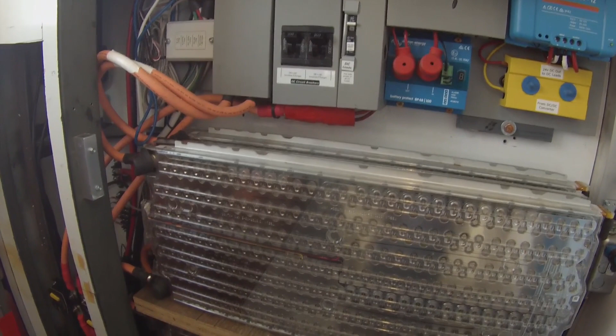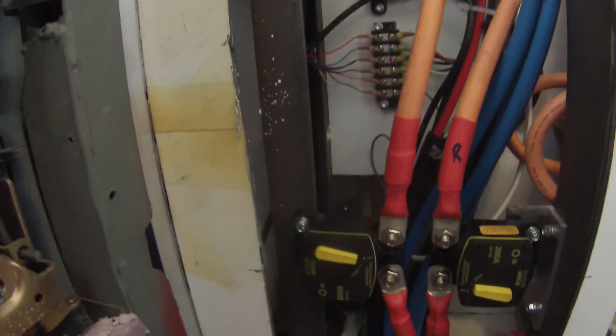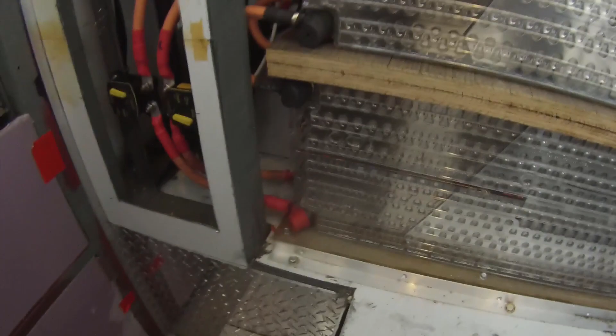Down here I have my terminal strips for power and for actuator controls. For safety, I've also installed two 200 amp isolation switches. Basically, that takes the positive coming from each bank. These front ones are a bank because they're 24 volts apiece, and my back ones are also 24 volts apiece, so tied together they're 48 volts. That kills the power running to the main breakers.